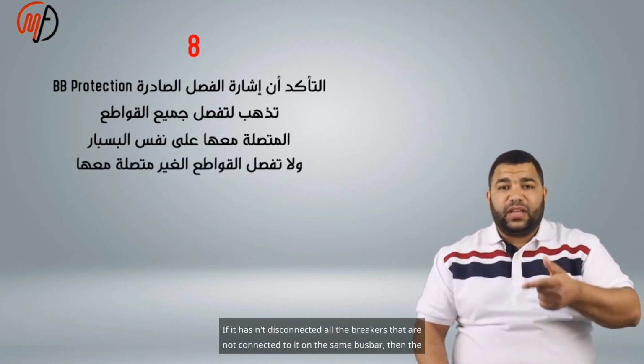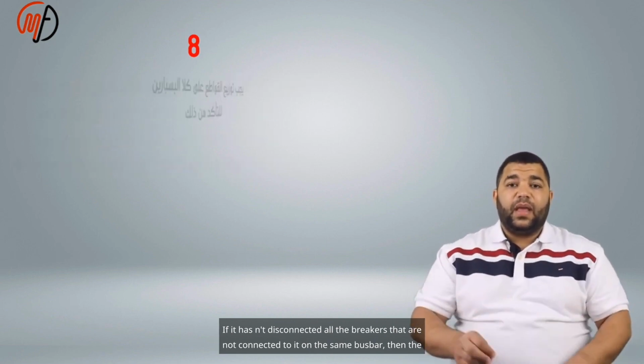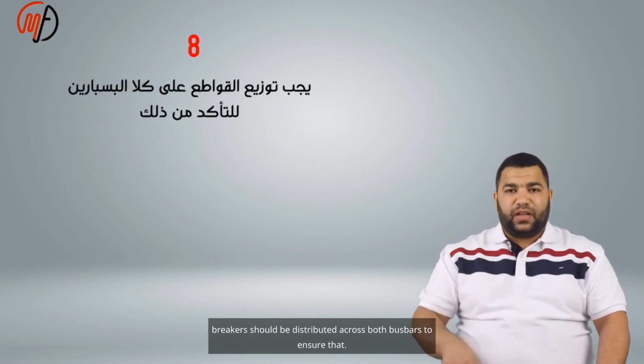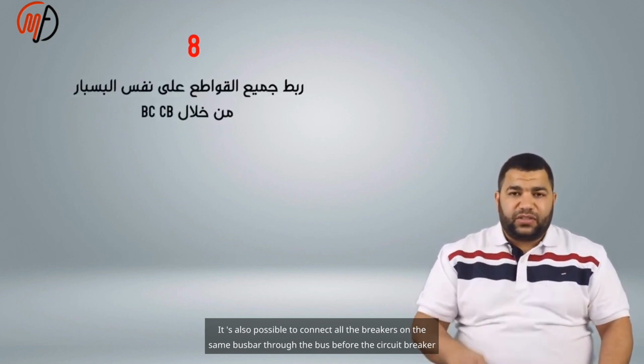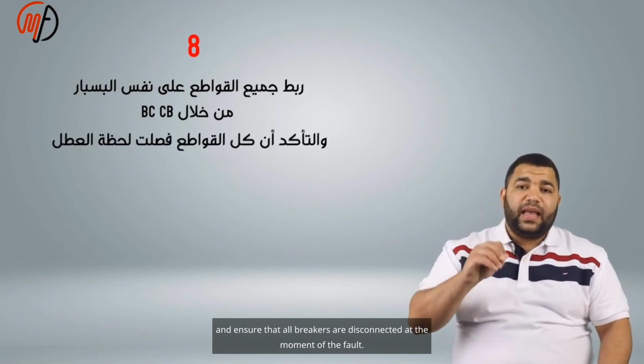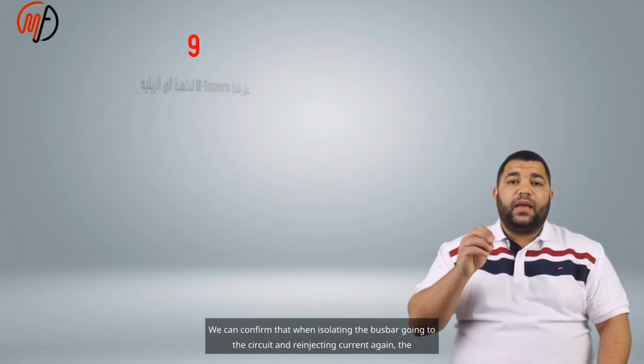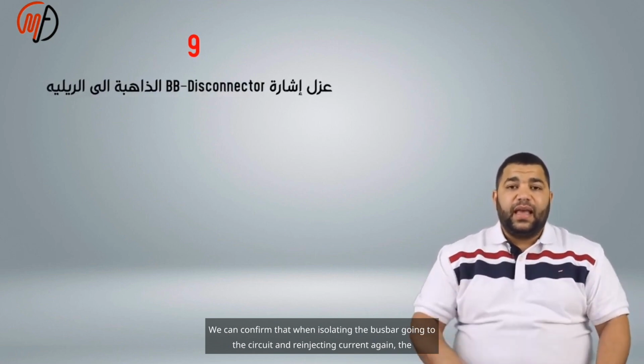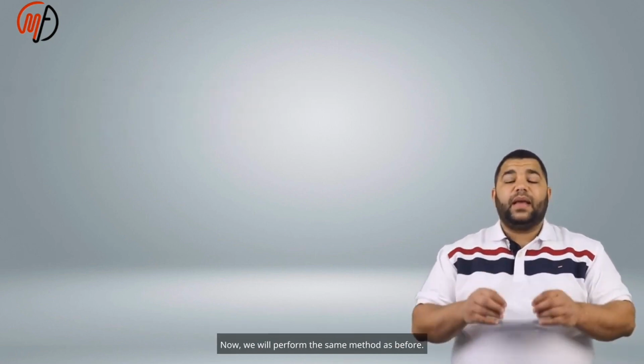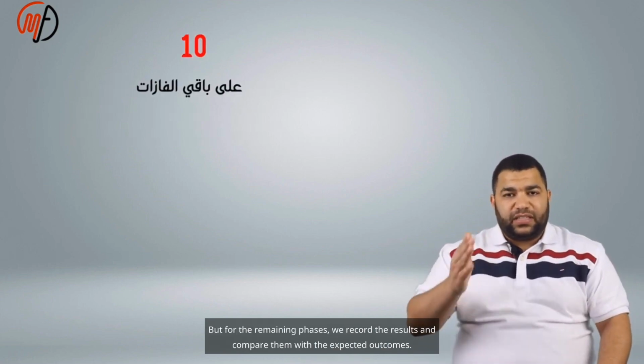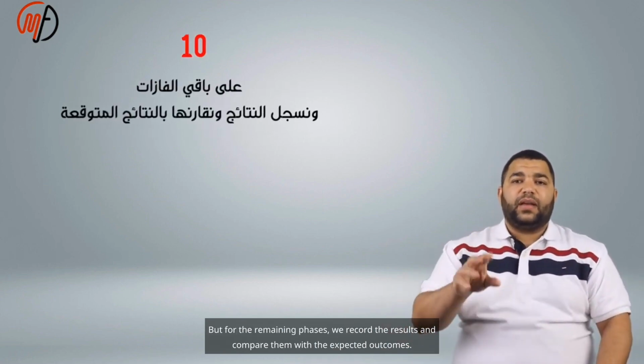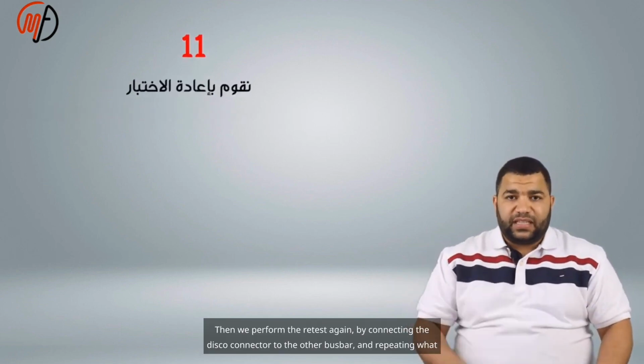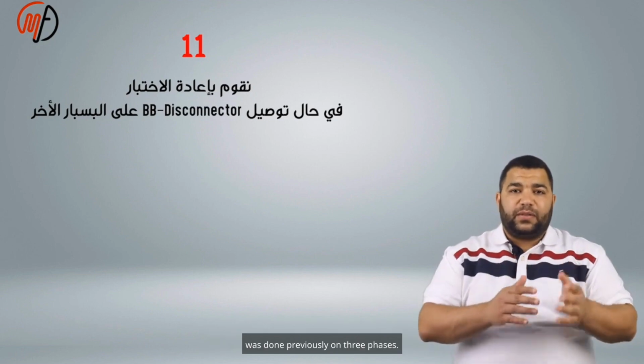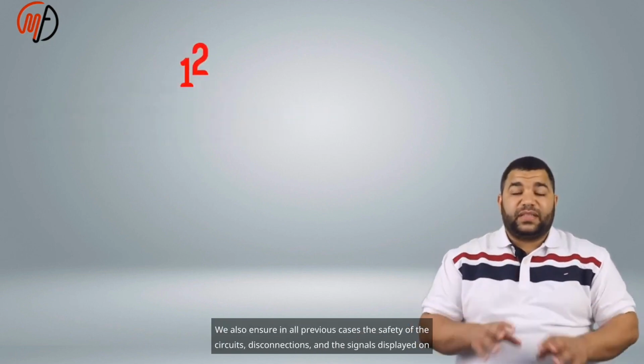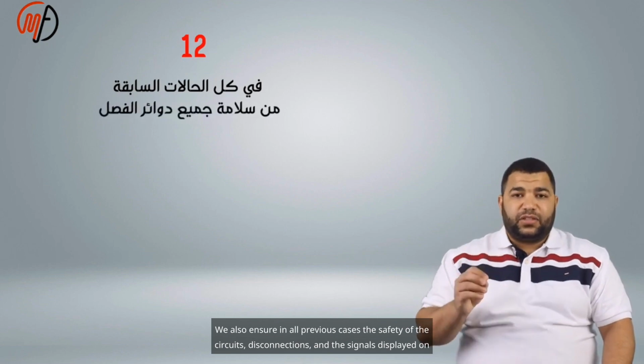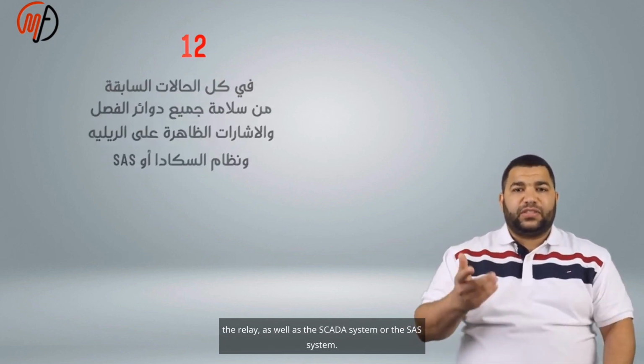If it hasn't disconnected all the breakers on the same bus bar, then the breakers should be distributed across both bus bars to ensure that. It's also possible to connect all the breakers on the same bus bar through the bus before the circuit breaker and ensure that all breakers are disconnected at the moment of the fault. We can confirm that when isolating the bus bar going to the circuit and re-injecting current again, the protection will not operate. Now we will perform the same method as before for the remaining phases, record the results and compare them with the expected outcomes. Then we perform the retest by connecting the disconnector to the other bus bar and repeating what was done previously on three phases. We also ensure in all previous cases the safety of the circuits, the disconnections, and the signals displayed on the relay, as well as the SCADA system or the SAS system.